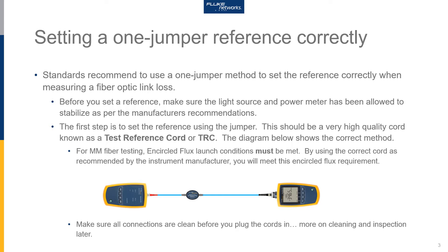Before attempting any fiber loss measurements, you need a correct reference — it's the most critical part of making the measurement. First step, and very important, you need to let the light source and power meter stabilize as per the manufacturer's recommendations. Not allowing instruments to stabilize is the biggest source of errors in loss measurements.